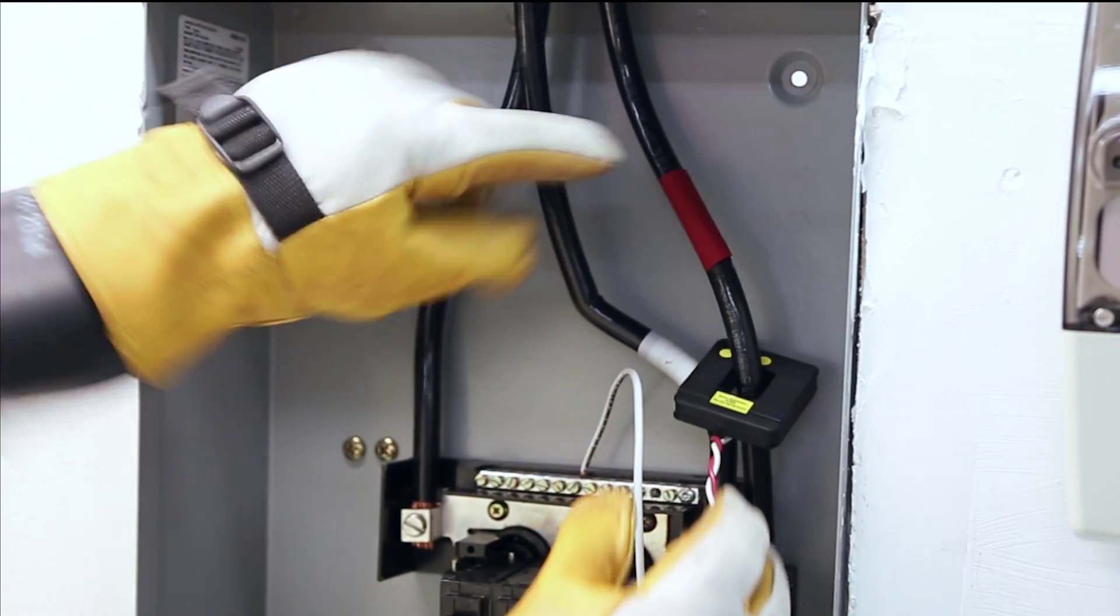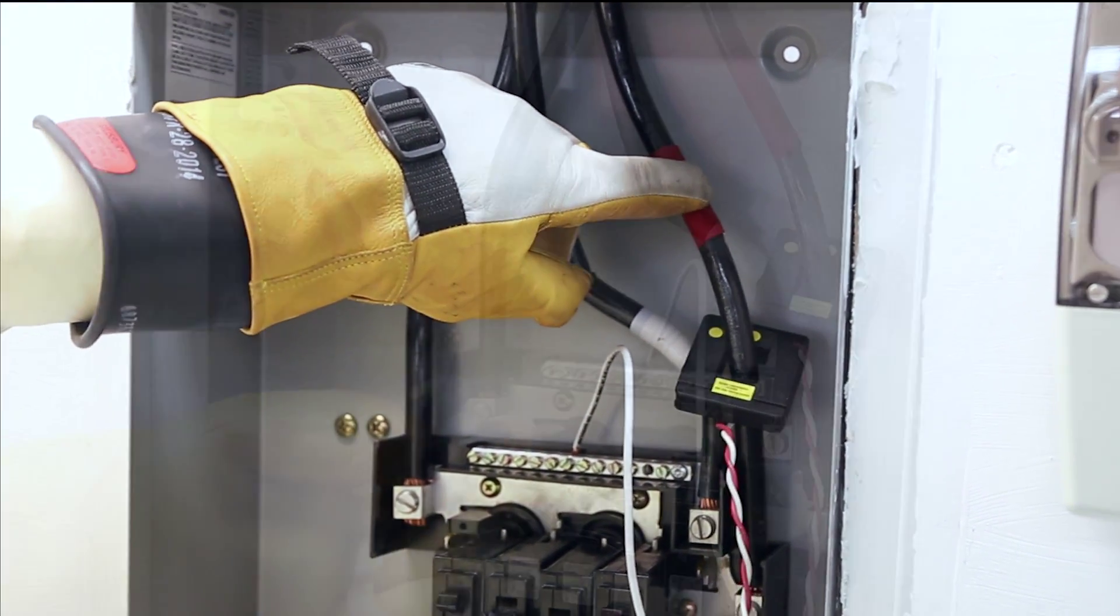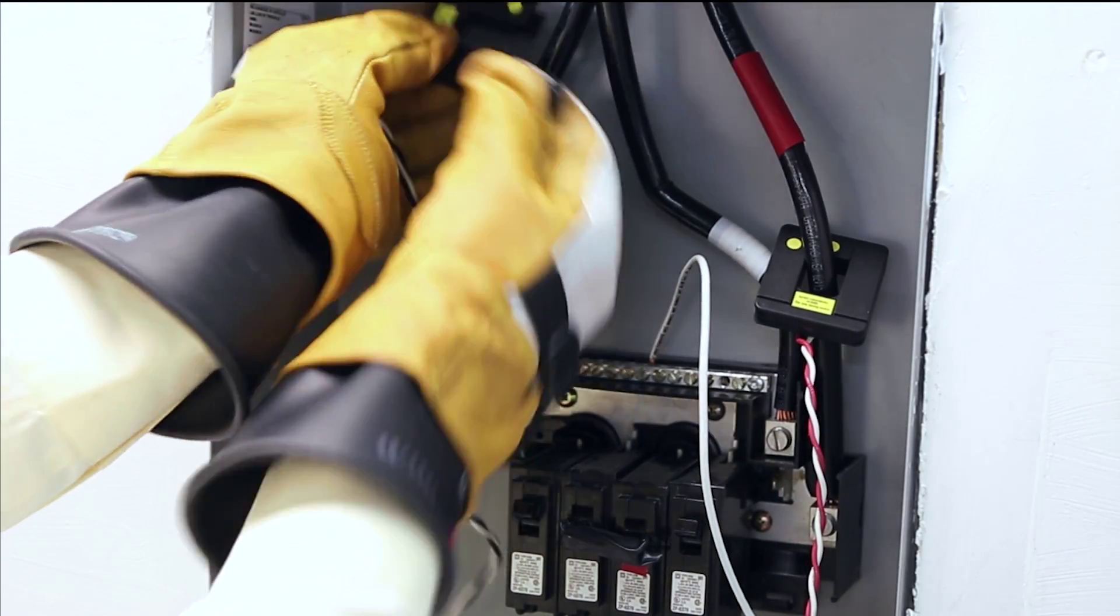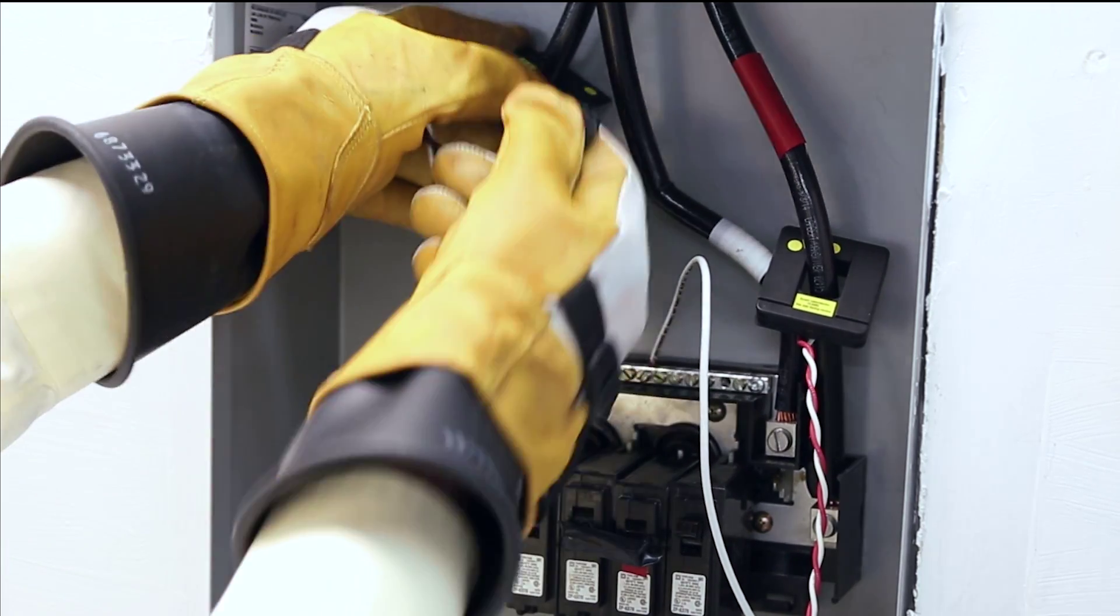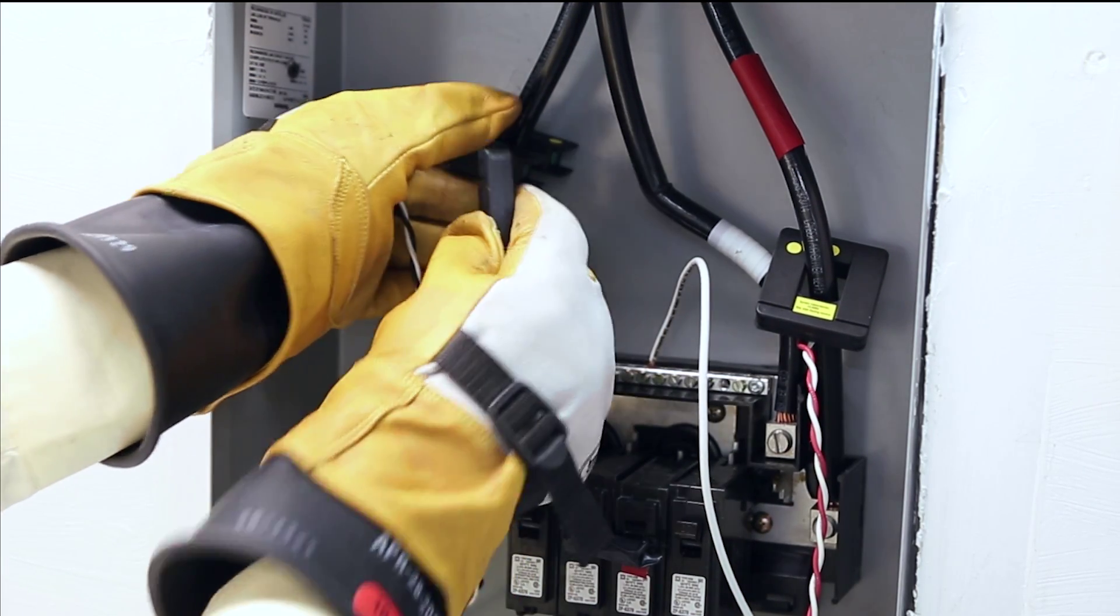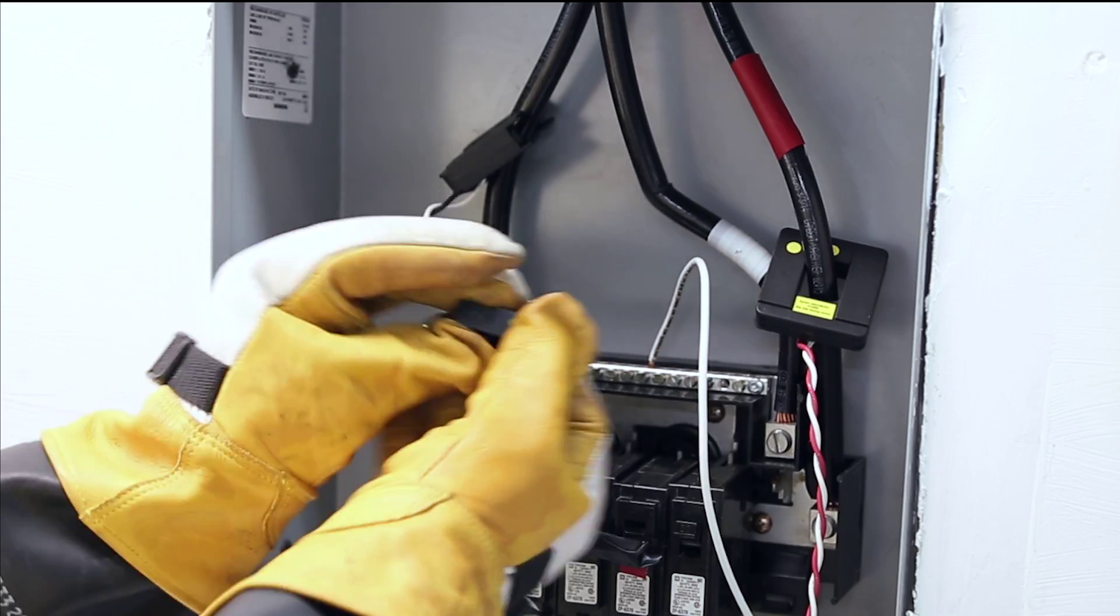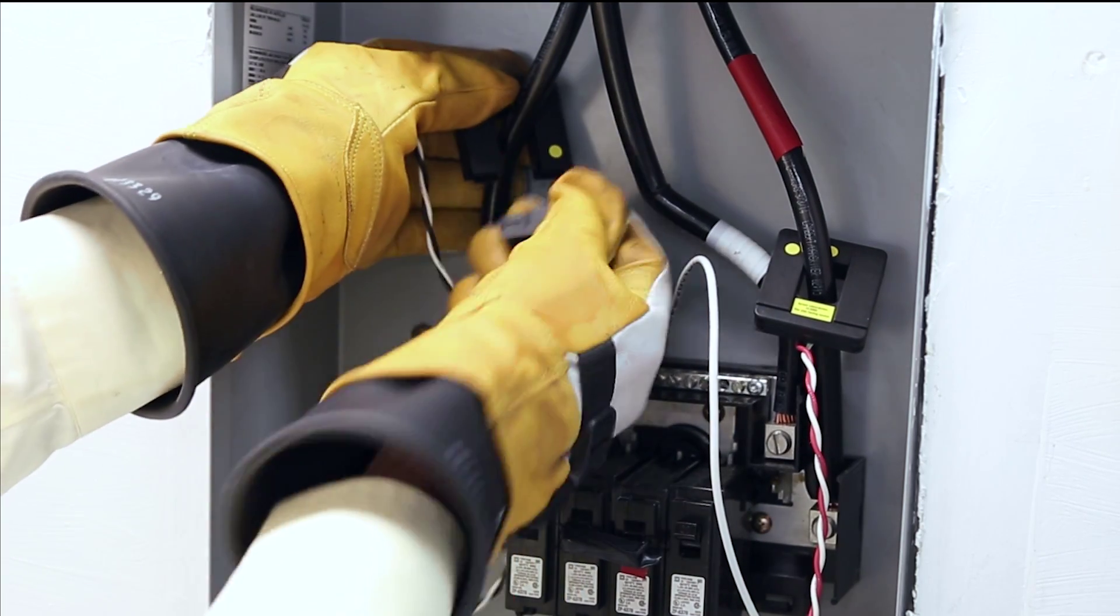The red CT goes with the red incoming power which matches your red voltage. Black line CT goes with the black line. Again, the dots are toward the incoming power. Make sure that the bar or the dot matches the bottom portion.